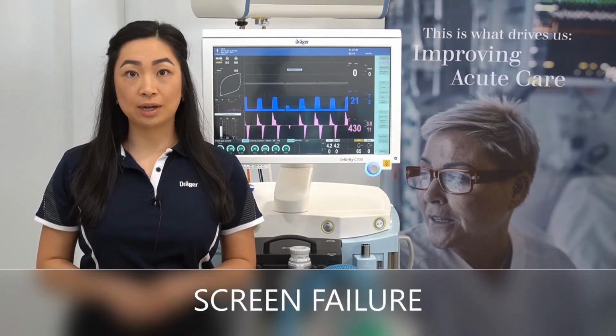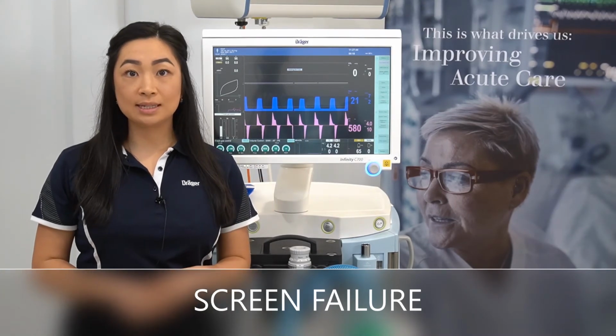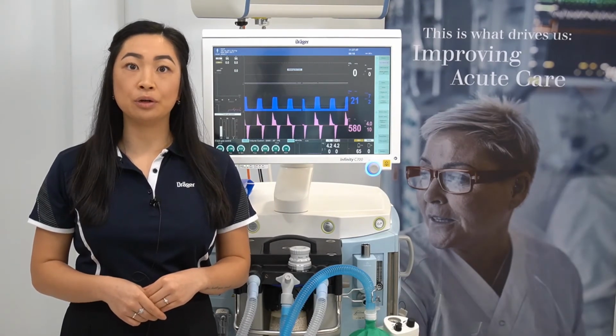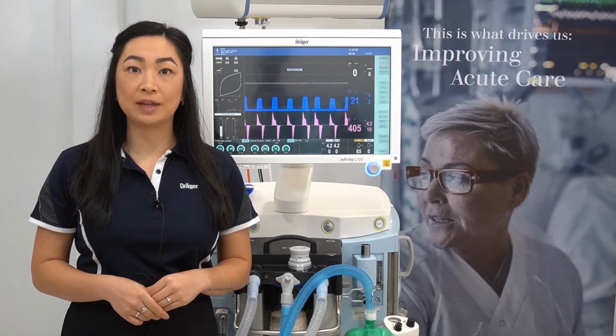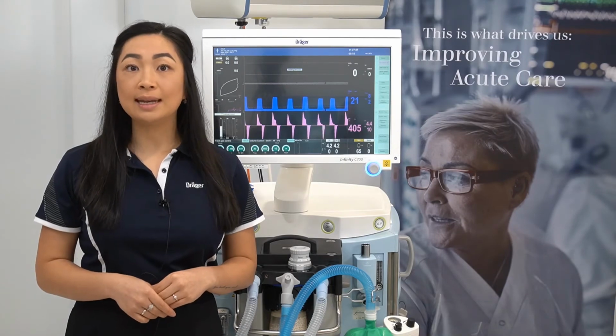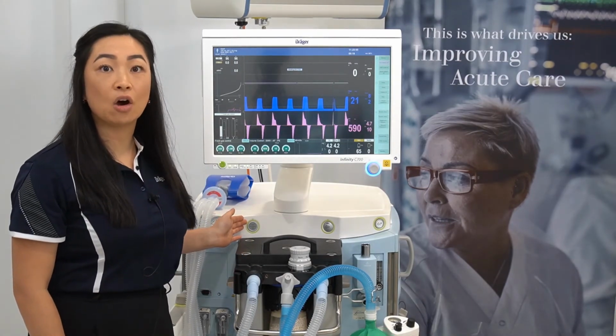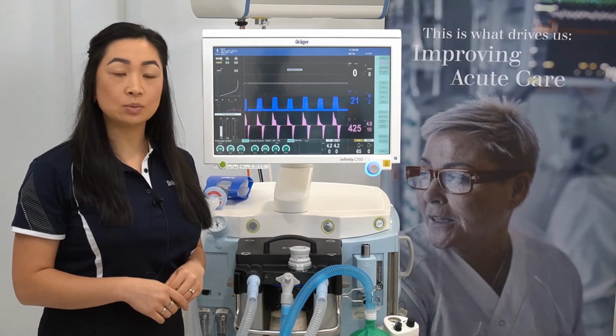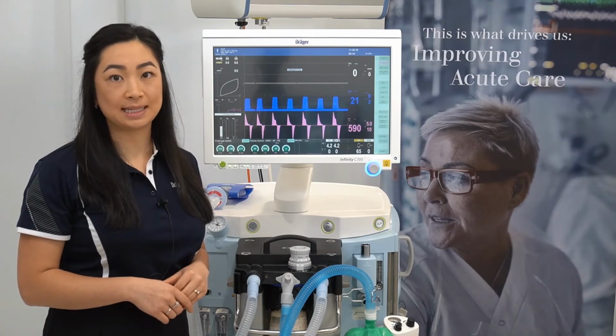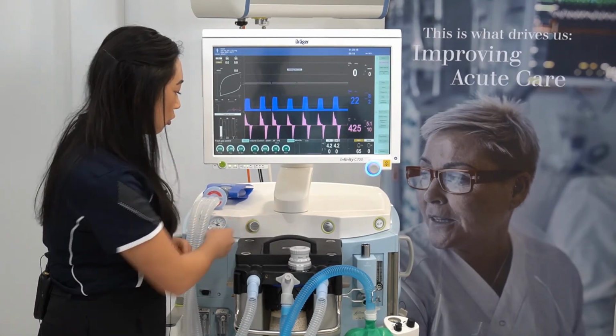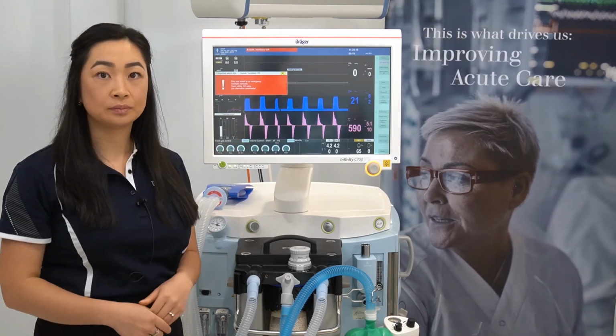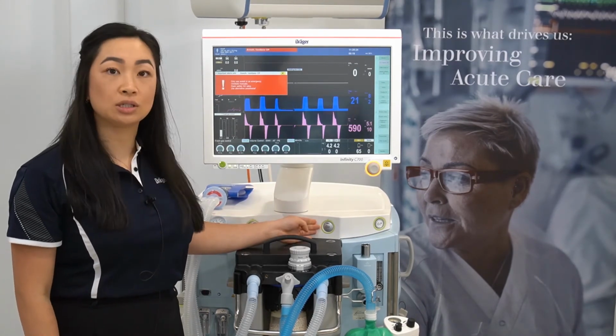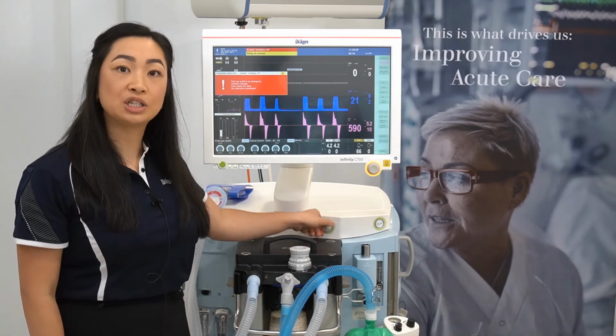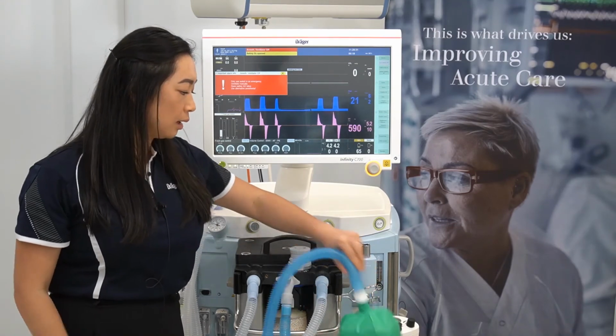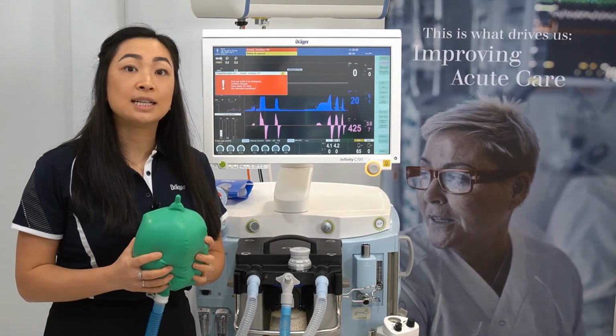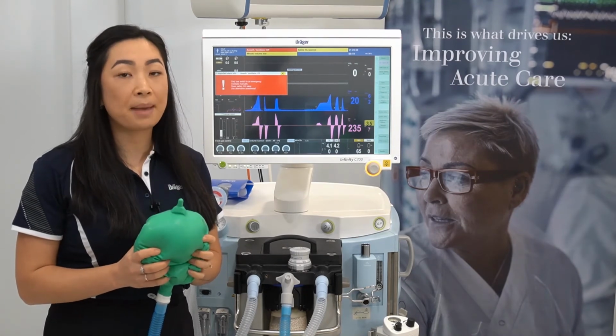In the event of a screen malfunction, or there is an error with the display, or the screen fails to recognise input, you will not be able to make adjustments to your ventilation settings. The user will then need to activate the anaesthetic ventilator off control knob. Activating this will switch off the ventilator and electronic gas mixing. To perform this, push in the control knob and turn counterclockwise. You will then need to activate your emergency oxygen delivery by pushing in the control knob and dialing up to your desired flow. Check your APL valve setting, transition to intravenous drugs, and start manual ventilation.